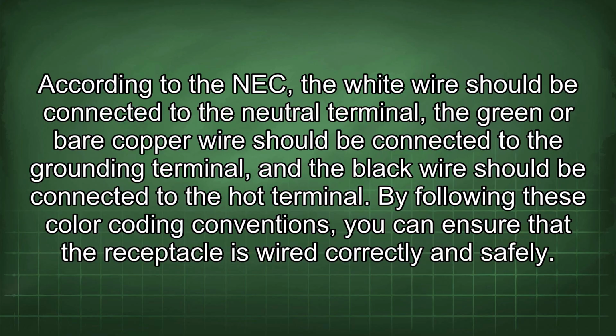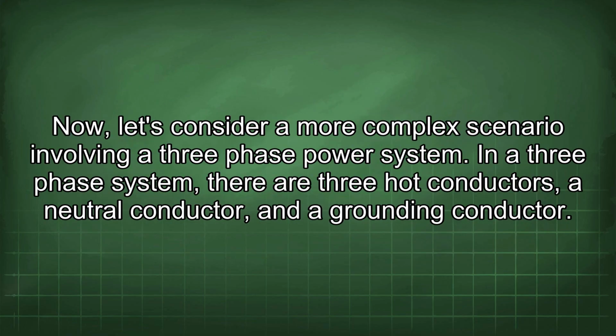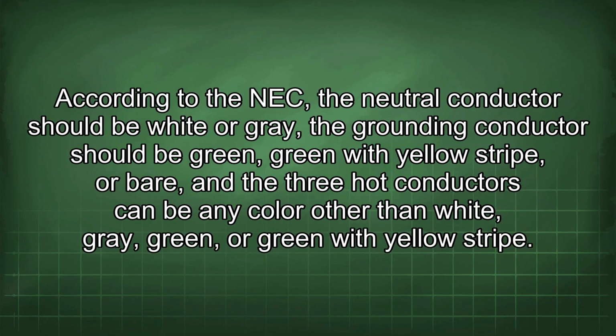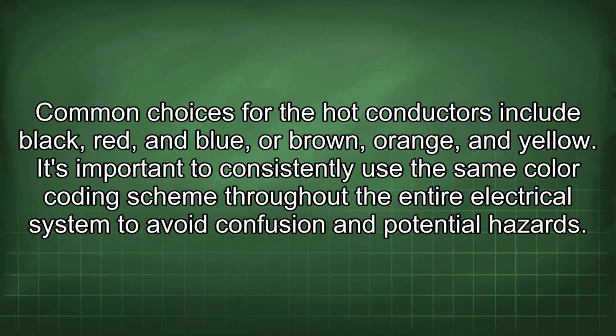By following these color coding conventions, you can ensure that the receptacle is wired correctly and safely. Now, let's consider a more complex scenario involving a three-phase power system. In a three-phase system, there are 3 hot conductors, a neutral conductor, and a grounding conductor. According to the NEC, the neutral conductor should be white or grey, the grounding conductor should be green with yellow stripe, or bare, and the 3 hot conductors can be any color other than white, grey, green, or green with yellow stripe. Common choices for the hot conductors include black, red, and blue, or brown, orange, and yellow.